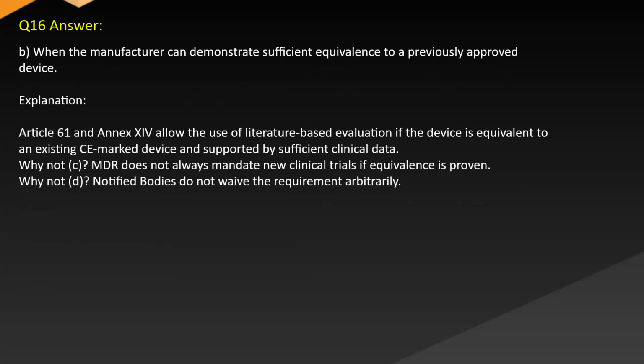Answer: B. When the manufacturer can demonstrate sufficient equivalence to a previously approved device. Explanation: Article 61 and Annex XIV allow the use of literature-based evaluation if the device is equivalent to an existing CE-marked device and supported by sufficient clinical data. Why not C? MDR does not always mandate new clinical trials if equivalence is proven. Why not D? Notified bodies do not waive the requirement arbitrarily.